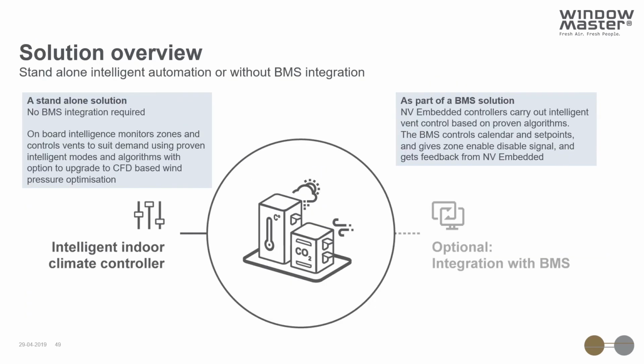As a standalone solution, no BMS is required. All of the intelligence is built into the controllers, and they can be configured to deliver a high level of control of the automated vents around the building, with the possibility of upgrading to CFD-based algorithms similar to NV Advance, without the requirement for a head end.